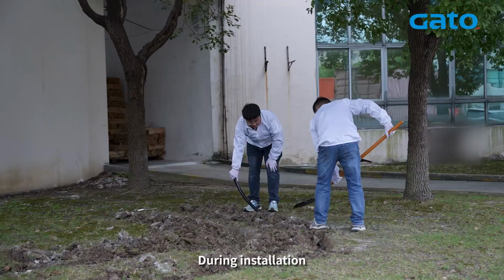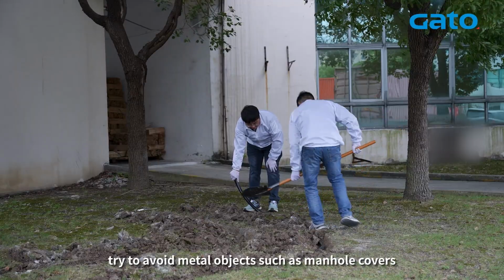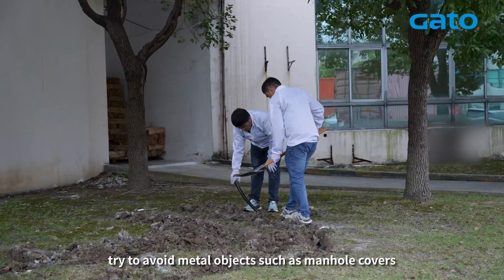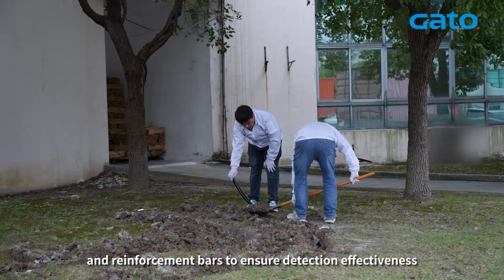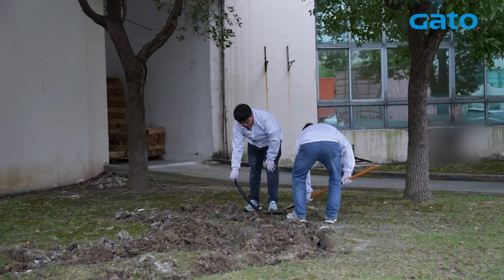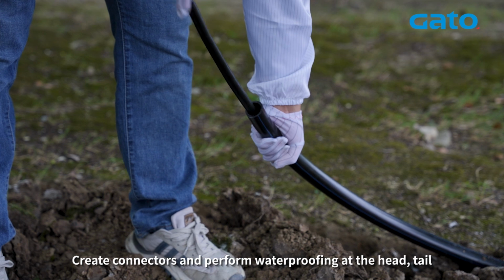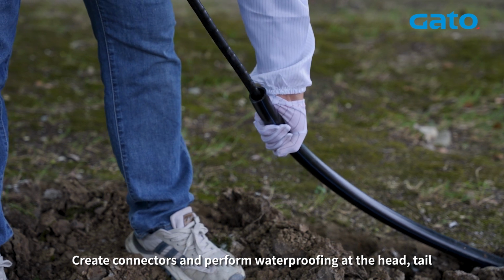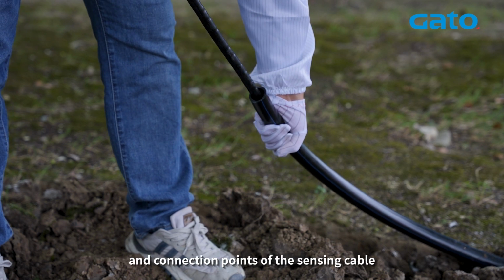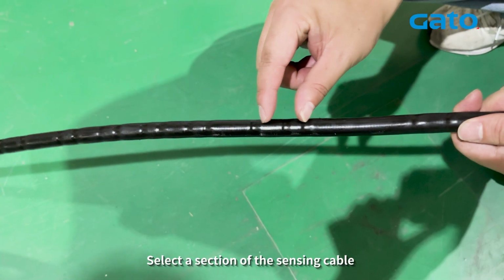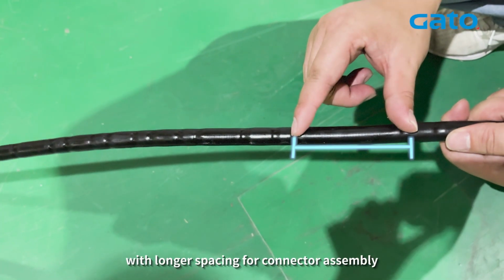During installation, try to avoid metal objects, such as manhole covers and reinforcement bars, to ensure detection effectiveness. Create connectors and perform waterproofing at the head, tail, and connection points of the sensing cable. Select a section of the sensing cable with longer spacing for connector assembly.